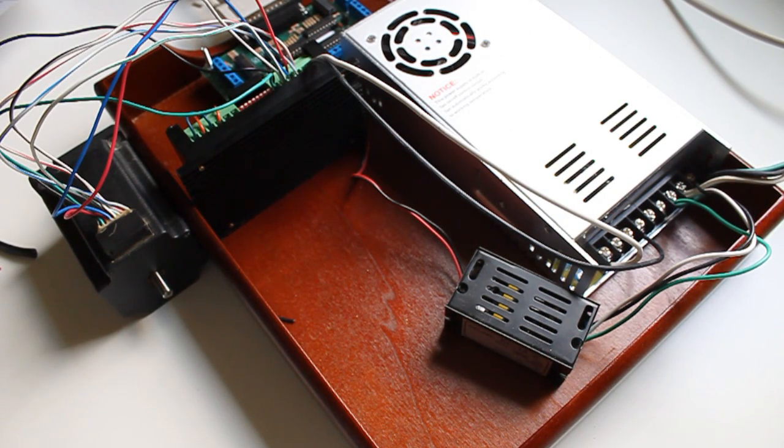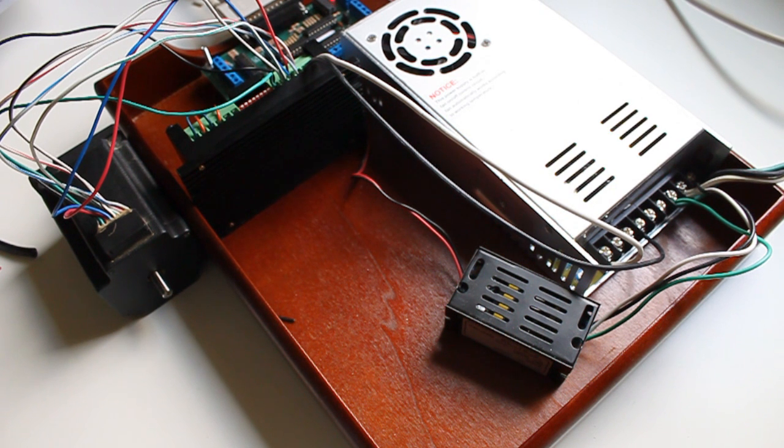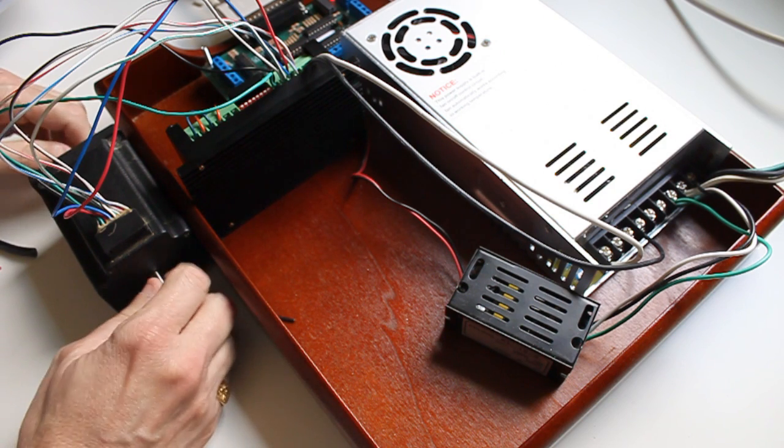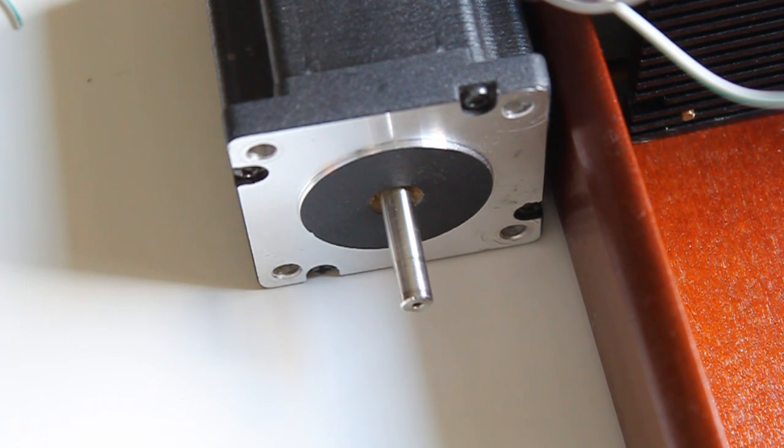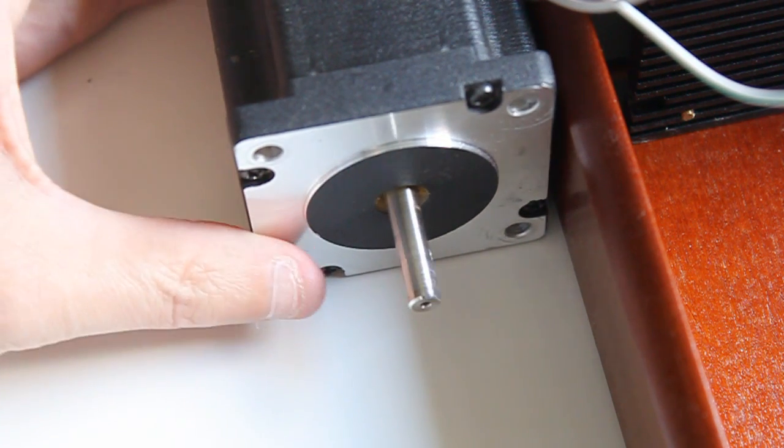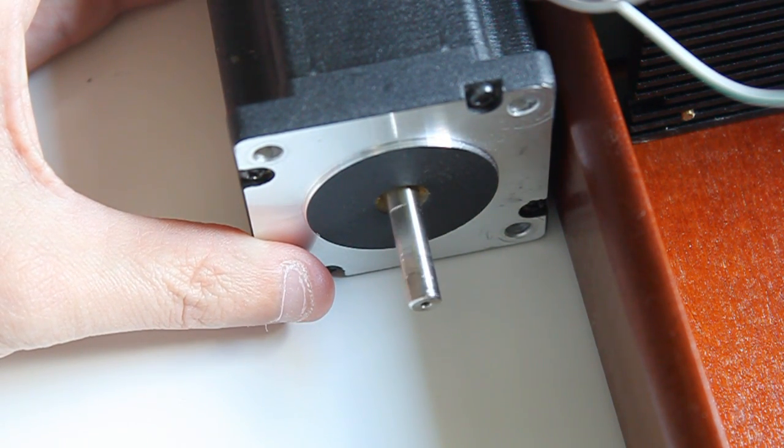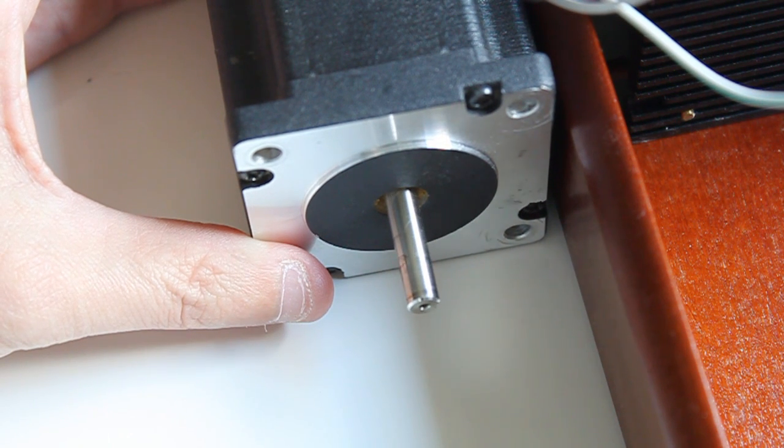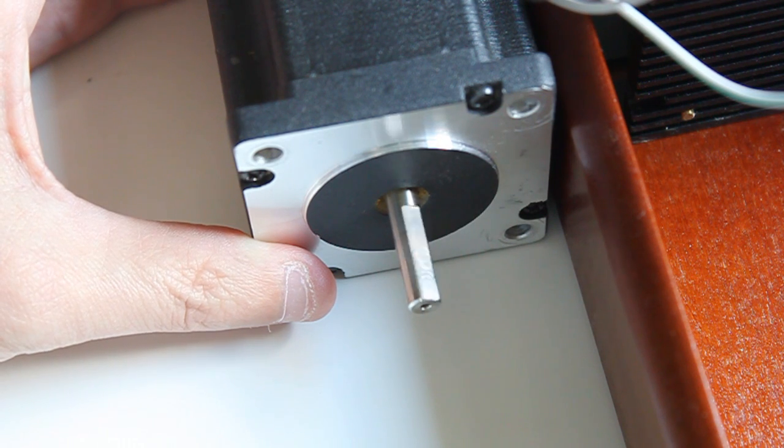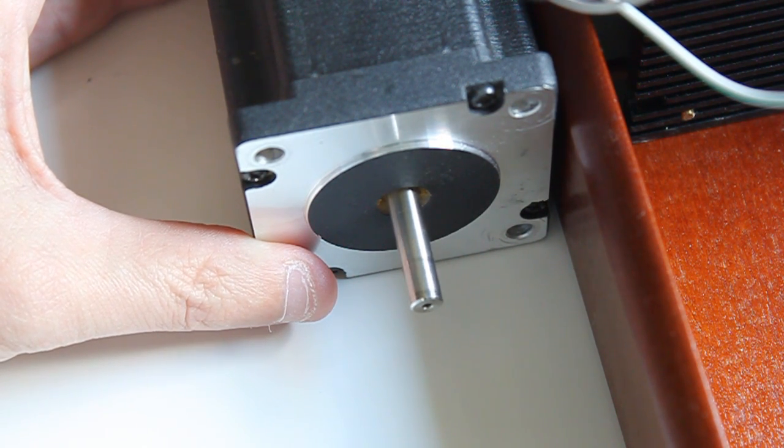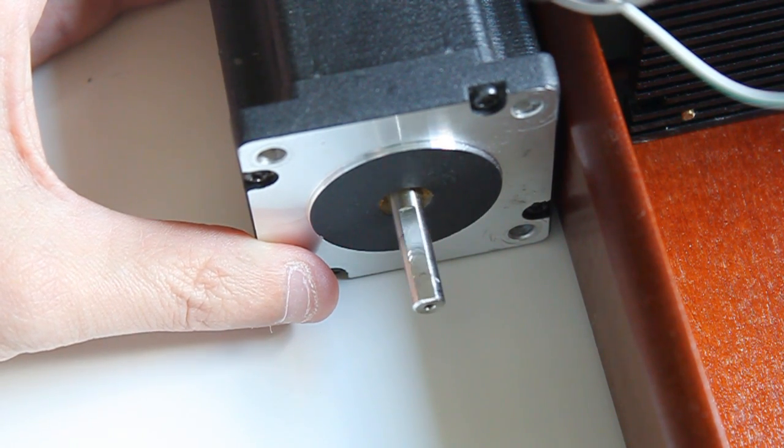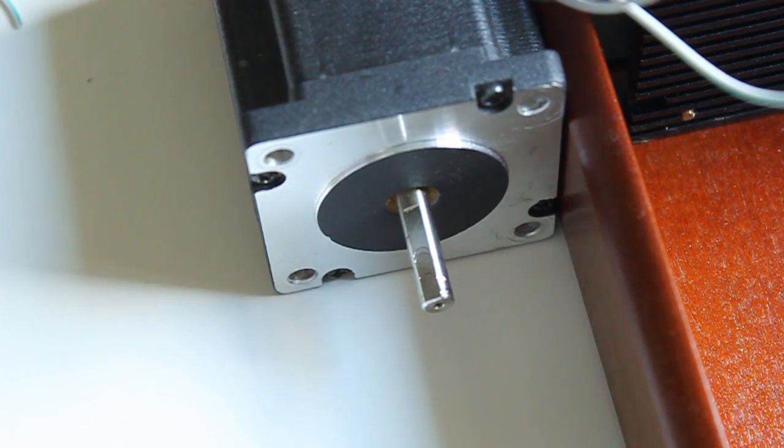Make sure to press reset. Now I'm going to plug in the system and see if the motor turns when I jog it. You'll notice you heard a thump. That's the motor engaging and providing torque. When I press the left arrow key, it should run. Looks like it's running clockwise. When I press the right arrow key, it's running the different direction. So this motor is set up correctly.